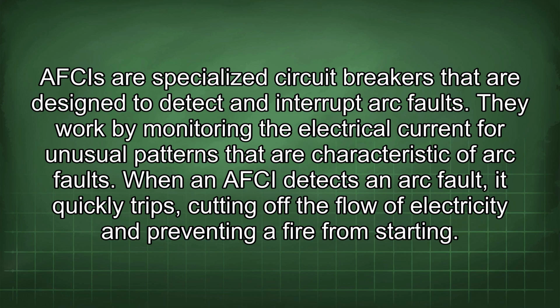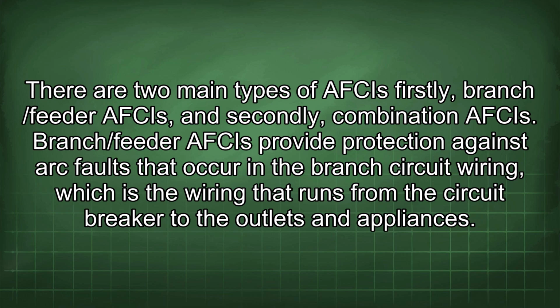AFCIs are specialized circuit breakers that are designed to detect and interrupt arc faults. They work by monitoring the electrical current for unusual patterns that are characteristic of arc faults. When an AFCI detects an arc fault, it quickly trips, cutting off the flow of electricity and preventing a fire from starting. There are two main types of AFCIs: firstly, branch/feeder AFCIs, and secondly, combination AFCIs. Branch/feeder AFCIs provide protection against arc faults that occur in the branch circuit wiring, which is the wiring that runs from the circuit breaker to the outlets and appliances.